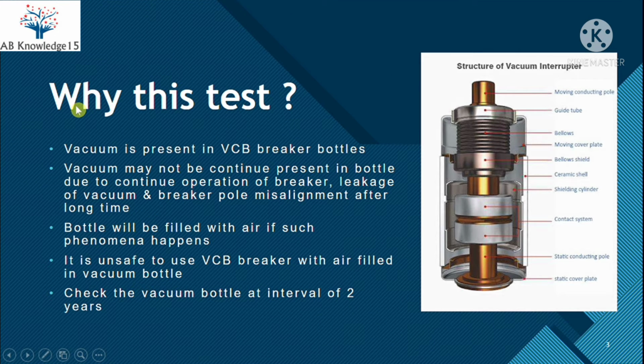Now, why is this test necessary? In this picture, suppose this vacuum bottle is filled with vacuum in normal condition, but the vacuum may not last long in this bottle due to the continuous operation of the breaker. After a long duration, leakage starts, the vacuum leaks out and air fills the bottle. This may also happen due to misalignment of the breaker poles. So we need to check this bottle after a long time so that its healthiness can be confirmed for continued operation.